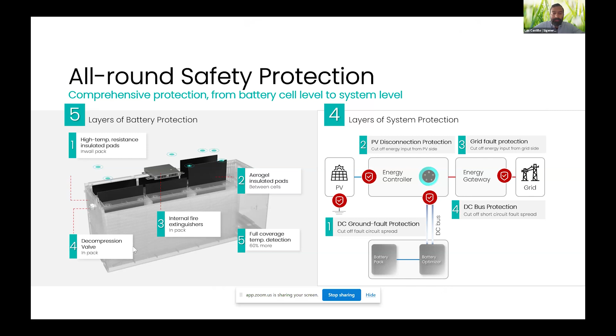All of these are last resort measures. The main layer of defense is the information from the sensors, and we've integrated AI algorithms for safety designed to predict a potential fault inside the battery pack. So we don't need to wait for the fire extinguisher to trigger to understand the battery pack has failed. The algorithm could understand a fault is inevitable, and the battery will be disconnected from the array. In this scenario, the installer will also get an alarm, a message saying the battery needs to be replaced.